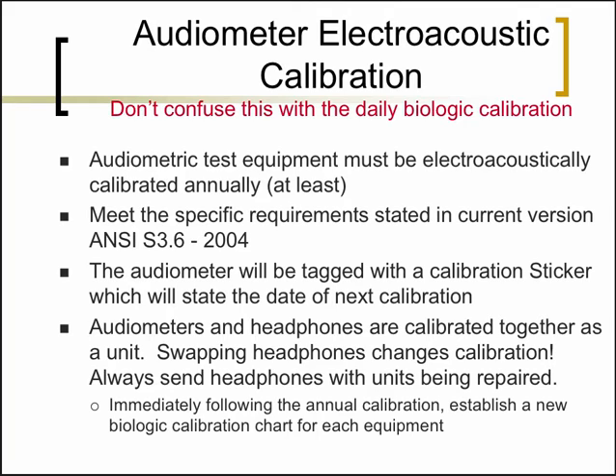Again, a word of precaution: when an audiometer is calibrated, it is calibrated with a particular set of headphone or insert earphone and bone vibrators. So they are calibrated as a unit. Although it might be the same company, the same version number, it's important that one doesn't swap the headphones. A headphone might be slightly off, but one would calibrate the audiometer to account for that variation in the headphone. So you have this very calibrated fixed output. Again, it's also important that immediately after the annual calibration, you set these biological calibration standards. In that way, for your daily calibration, you'll have something to confirm on a daily basis.